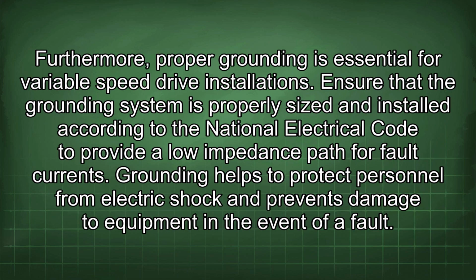Furthermore, proper grounding is essential for variable speed drive installations. Ensure that the grounding system is properly sized and installed according to the National Electrical Code to provide a low impedance path for fault currents. Grounding helps to protect personnel from electric shock and prevents damage to equipment in the event of a fault.